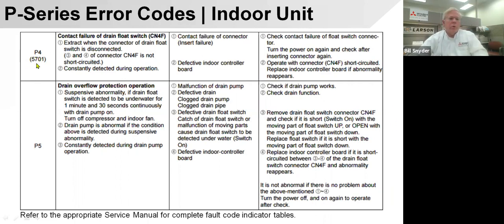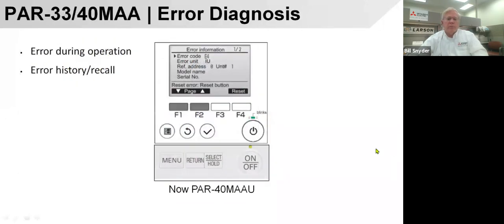P-series error codes show up like this on the controls. It'll be like a P4 or like a 5701 would show up, or a P5. That's the type of codes. You go look it up and it tells you here P5 is a drain overflow protection, and you'll have to find out if the drain is plugged or if the float switch is bad. Kind of walks you through what to look for and how to fix it. Pretty simple, makes it pretty easy.